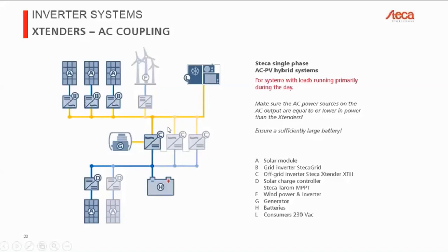Now there are 2 points that you need to keep in mind. The first one is what happens when the battery is empty, and the other one is what happens when the battery is full. Let's look at what happens when the battery is full. The Xtender somehow needs to give a signal to your grid-connected inverters, or it could also be a grid-connected wind generator, for example, that is made for injection into the grid. You somehow need to signal to these energy sources that the battery is full, that you no longer require energy.